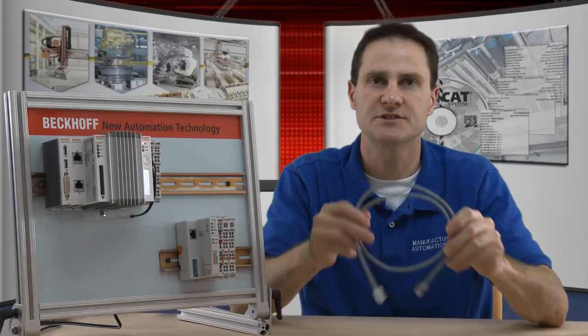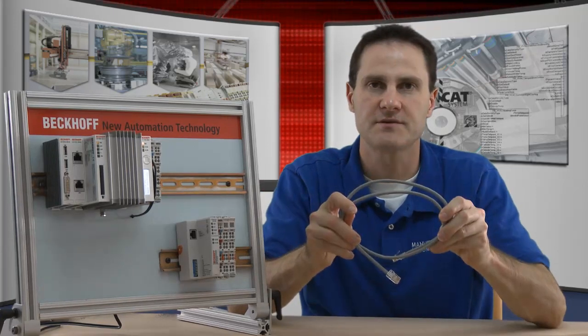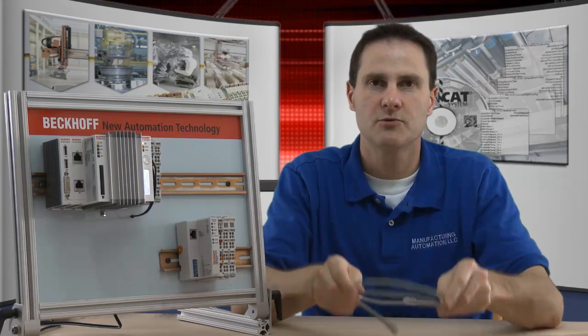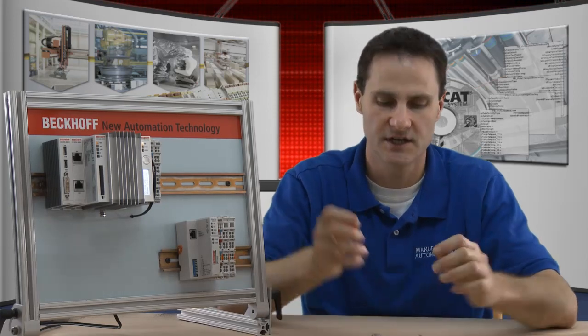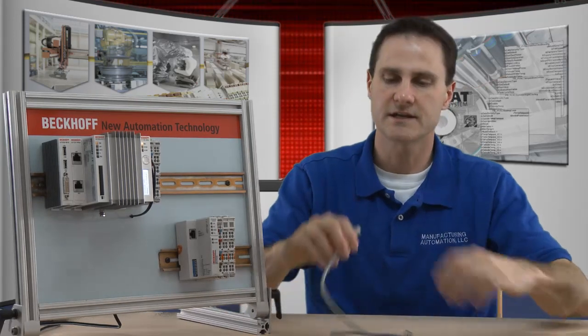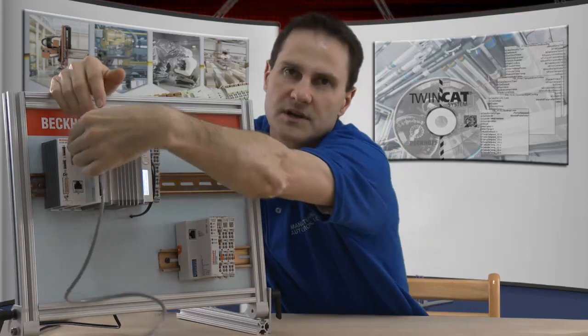For communications between our development PC and the CX processor we will be using Ethernet. So for the physical Ethernet connection we simply need a straight through Ethernet cable. We will not be needing a crossover cable or a hub or a switch because the CX processors, with the exception of the CX1000, support Auto MDIX, which simply means you can use a straight cable and it auto detects whether it needs a crossover cable and automatically adjusts. So let's go ahead and plug this in.